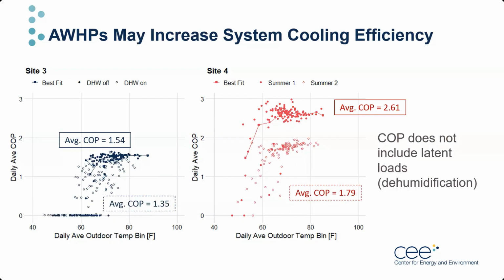Site 3 has quite a few days with 0 or nearly 0 COP. These data points are typically days where there is both heating and cooling, which cancel out in our math to produce very small daily cooling COPs. There are also some days here where there was very little cooling delivered, even if there was no heating that day.